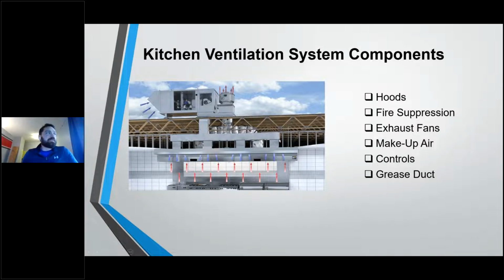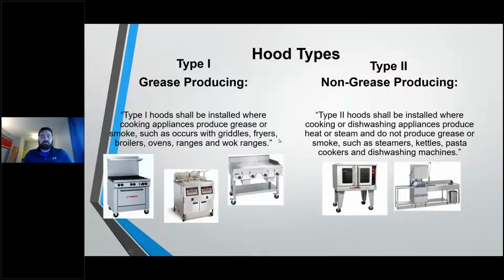So first and foremost, the first part of this kitchen ventilation system, pretty basic, but it's the hood. So hoods in the market, you're going to have either a type 1 grease producing hood that are listed to UL 710 listing standards, or you're going to have a type 2 hood for a non-grease producing application, for a heat only application, or for when we have a condensate or a dishwasher fan in here. It's pretty straightforward, and again, code's going to dictate a lot of what type of system you're going to go to.